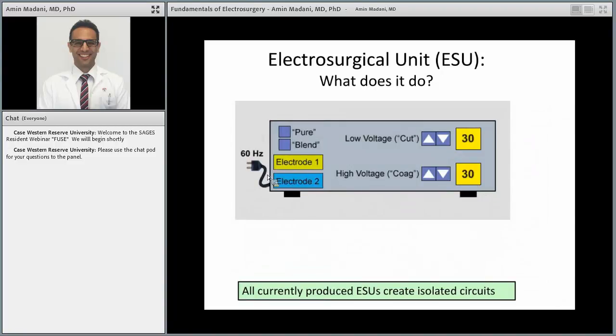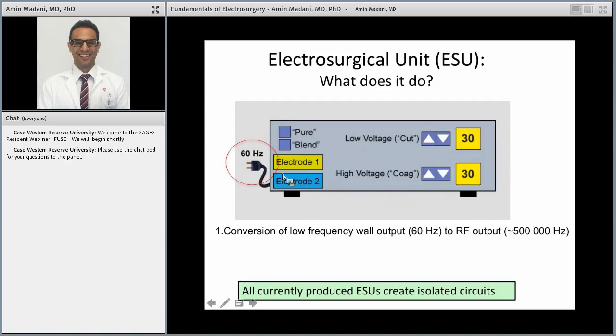Number one, it converts the frequency from the wall output to a much higher frequency, radio frequency output. The reason behind that is because you notice how when you activate the device on your patient, the patient doesn't get electrocuted. They don't go into cardiac arrest. Well, the reason is that you have increased the RF output to a high frequency to a point where the muscles and the nerves don't depolarize when you activate the device. So it surpasses the ability of muscles and nerves to depolarize, and therefore you prevent them from being electrocuted. So that's the first thing.